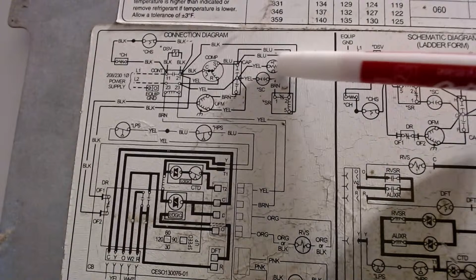All right, so get back to our compressor here. So coming off of 21, common, off of our start relay, comes up over here to our capacitor. And that's going to our Herm side of the capacitor, because the other side of that comes off and goes to the start of your compressor.